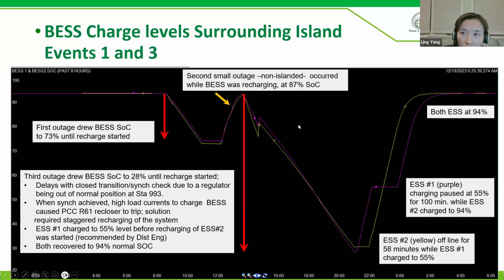Also, during the faults, when the battery was trying to sync back to the system, I believe one of the voltage regulators along the distribution circuits, on one of the phases, had its tap stuck, and there were difficulties for the battery plants to resync back to the system. So that is some of the real operations problems that we can potentially encounter in the real world.